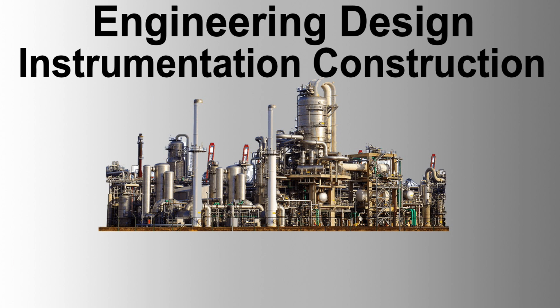Where this is not the case, the internals and the actuator shall be removed on site, and a temporary blind bonnet shall be fabricated locally. The trims shall only be installed after pressure testing and flushing.